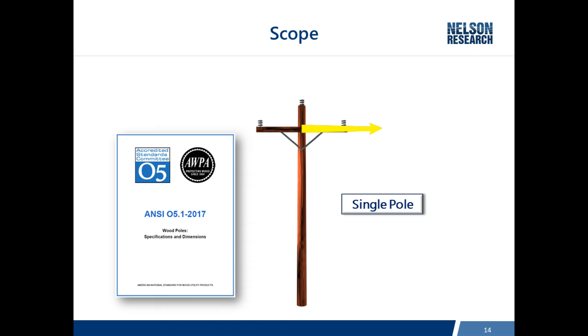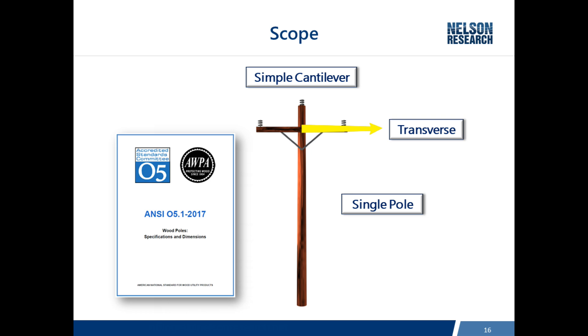The most often used standard is ANSI O5.1. In the scope, it clearly lays out that this standard addresses single poles in a simple cantilever installation — meaning it's fixed at the ground line and bends at the top. It also addresses only transverse loading, which is the wind load blowing on the wires trying to push the poles over sideways. All of the strengths in this standard are specified at the ground line of a pole.